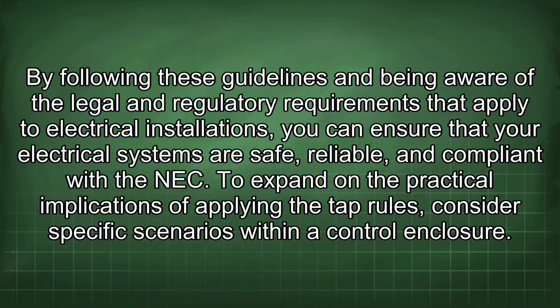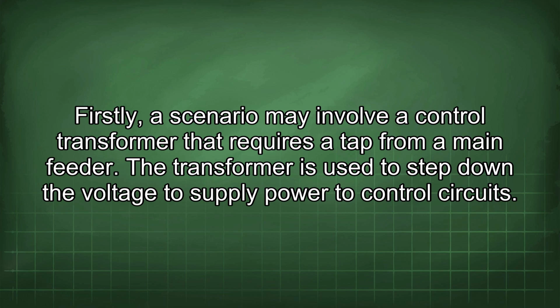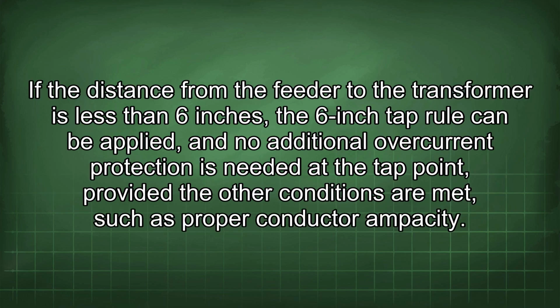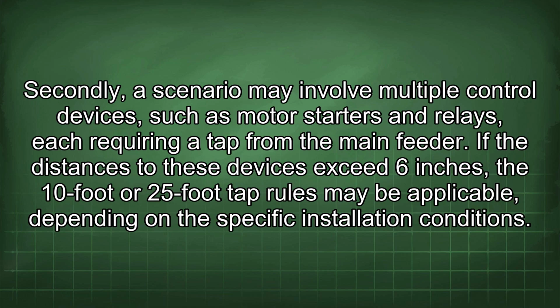To expand on the practical implications of applying the tap rules, consider specific scenarios within a control enclosure. Firstly, a scenario may involve a control transformer that requires a tap from a main feeder. The transformer is used to step down the voltage to supply power to control circuits. If the distance from the feeder to the transformer is less than 6 inches, the 6-inch tap rule can be applied, and no additional overcurrent protection is needed at the tap point, provided the other conditions are met, such as proper conductor ampacity.